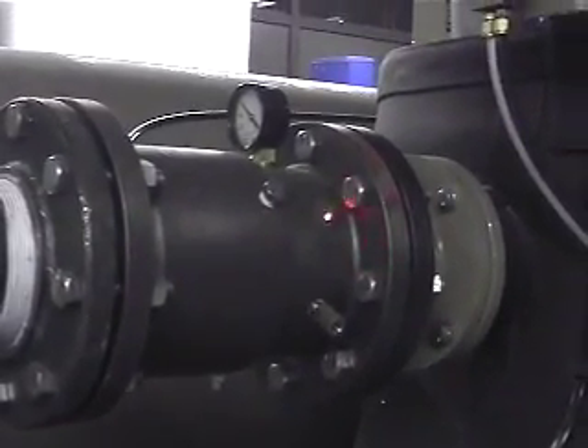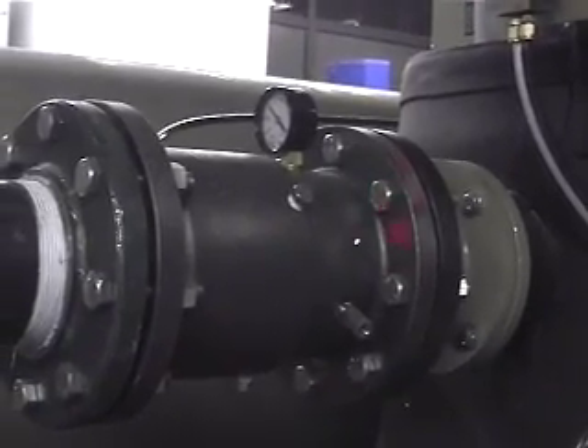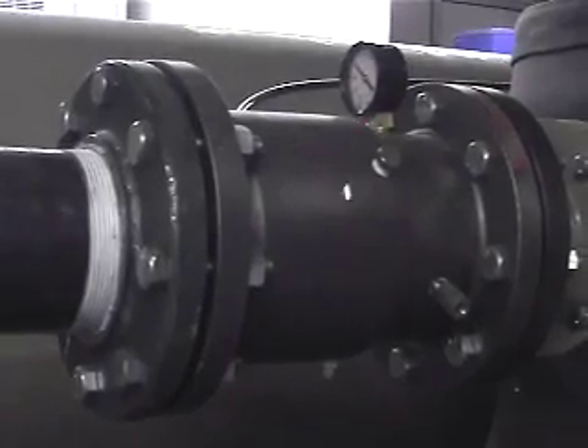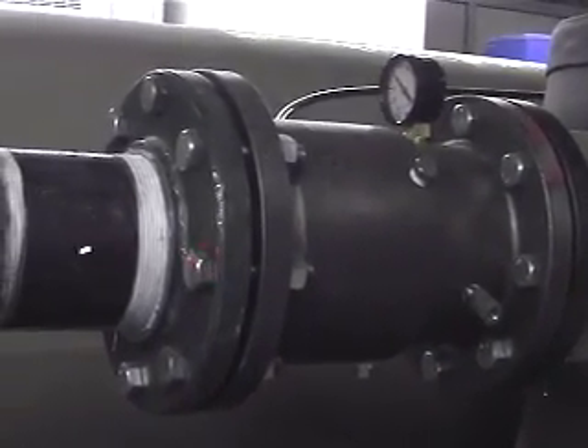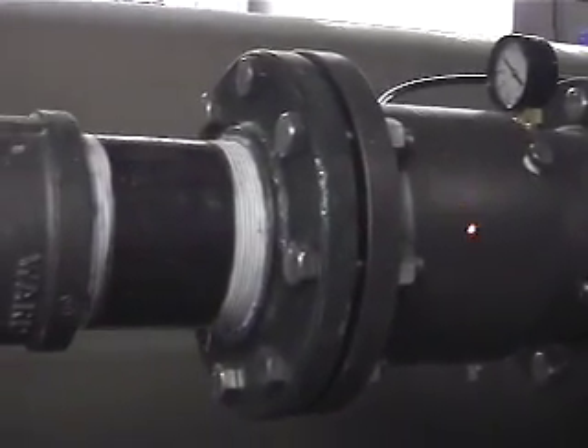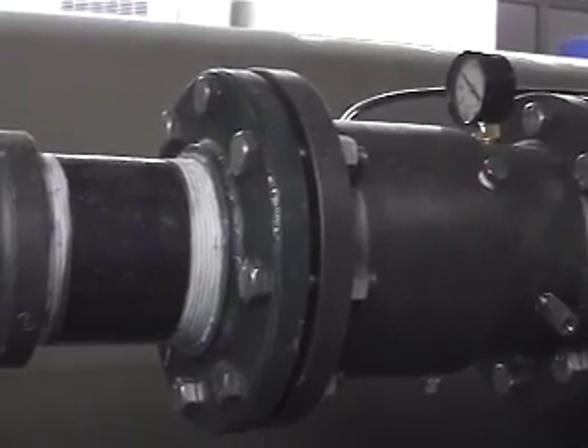We talked about the rupture guard. This right here is your rupture guard. Right there where you see my pointer, there's a rupture disc. It's an alloy steel that will break loose at 15 psi. Once that breaks loose at 15 psi, there's a spring with a relief valve right there. That spring opens up and relieves all the pressure up into the drum inside. At 13 psi, that spring reseats itself. That way you're not going to lose your low charge.